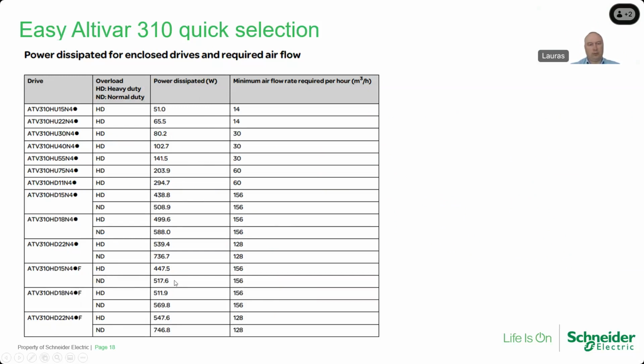In normal duty application, the heat is higher. Why? Because the nominal current is higher, and then if we have nominal load, the heat will be higher because the nominal current is high. So it's not a mistake, it is like this. So when you're calculating the total heat in the enclosure, please take care and pay attention to what kind of value to take.